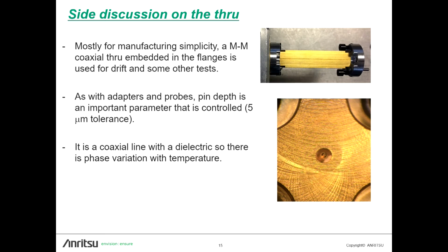And as you might guess, pin depth control is much more important than at lower frequencies, and this is holding about a 5 micron tolerance on that. And there is a coaxial line with dielectric inside, so there is a phase variation of the structure with temperature. But it is an interesting device, just as a passive artifact, and use that for some verification kinds of topics.